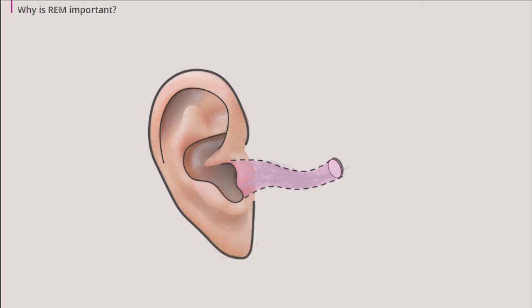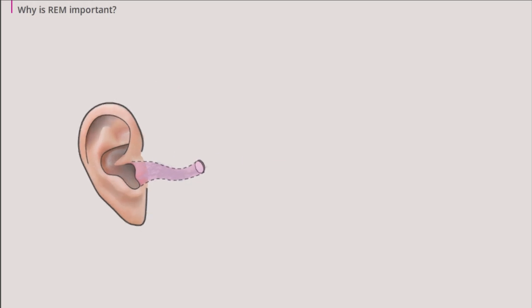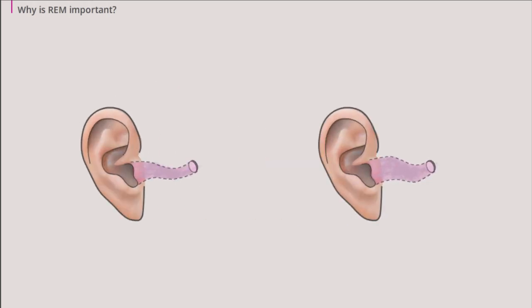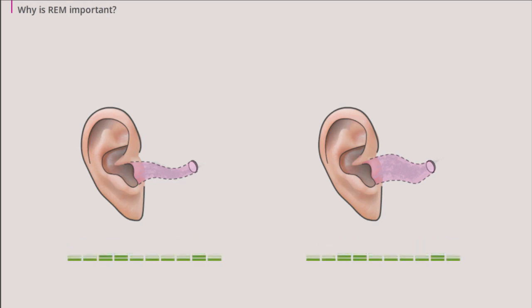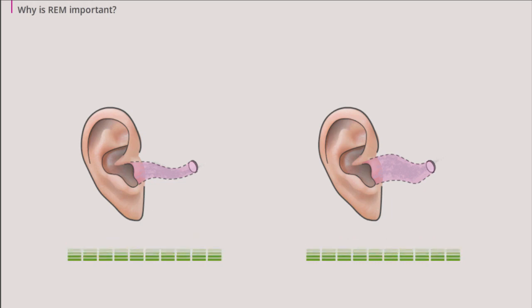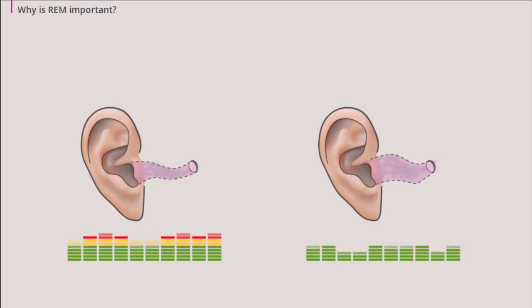This means that if a person with very small ear canals and a person with very big ear canals are fitted with the exact same average gain, the person with small ear canals will be over amplified and the person with big ear canals will be under amplified.